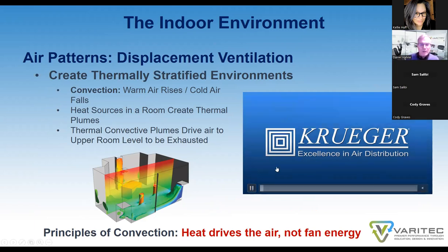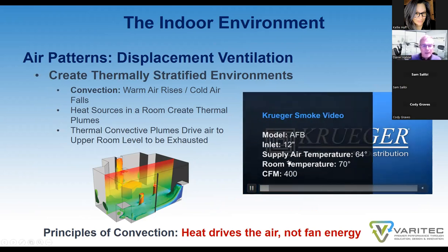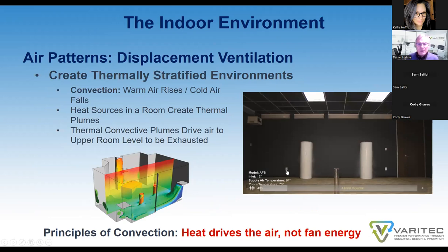So displacement ventilation is very attractive, and I've got a video here, hopefully it all starts up, that should demonstrate how a heat source moves air in the space, not high velocity discharge air that otherwise requires fan energy to bring that air at high velocity. In this video, actually taken by our manufacturer of displacement ventilation products, Krueger, they demonstrate how a heat source at the opposite end of the room draws smoke-filled air released from displacement diffusers to its location because of the convective plume, and that convective plume is drawing room air to it, and you'll soon see the smoke of the supply air rising off the heat source to the upper level of the room.